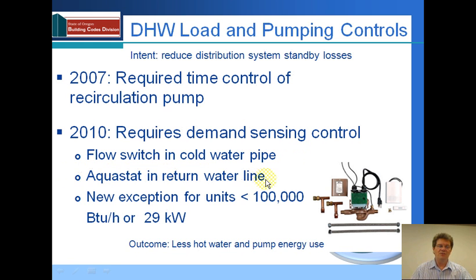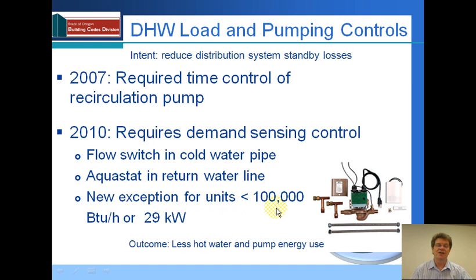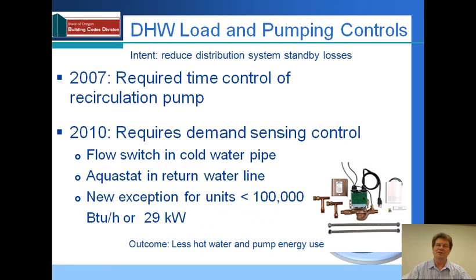The Aquastat requirement allows the pump to be turned off and save pump energy once the system is warmed up and it doesn't need to continue. There's an exception on these more sophisticated controls under 100,000 BTUs per hour, which is about 29 kilowatts. So for very small systems, this control wouldn't be required.